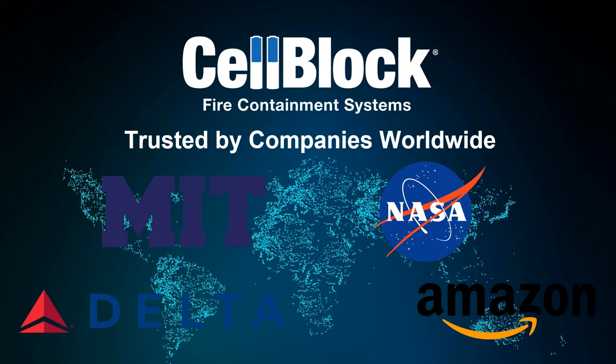And we're focused on that because we need that to be part of the incident kit. So our incident kits are meant to have everything on board that you need to address a fire. So the EHS kits, these things work just like a first aid kit. It's mounted on the wall at the factory or the facility. If there's an incident, they open up the bag, they put the gloves on, they grab the suppression pillow, they throw that on the incident, you take the fire blanket that's in the kit, you put that over the whole shooting match. Then if you have one of our drums, you pick the thing up and you put it in the drum with the Cellblock X. And that's a complete procedure to handle a lithium ion battery fire.